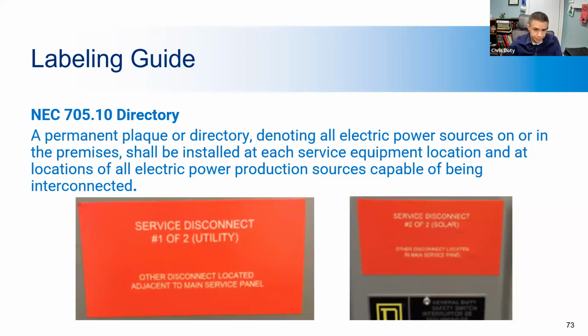Here we have the service disconnect labeling that's required. All service disconnects have to be labeled with permanent plaques. And here you can see it's good practice to tell, on each of them, where the other one is. Because if you only shut down one, you could still have an energized system. If you just say this is the first service disconnect, one of two, and you don't tell where the other one is, it's much less useful.